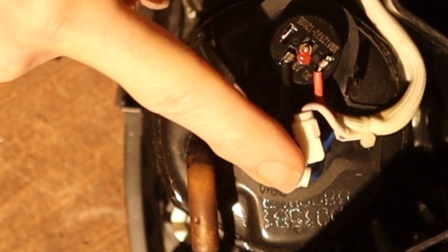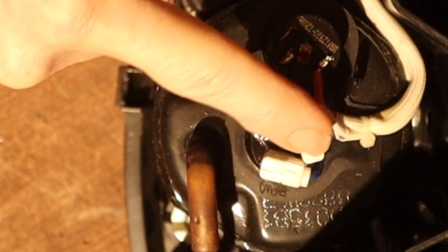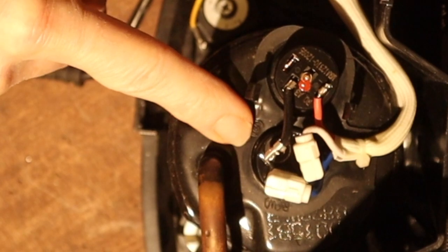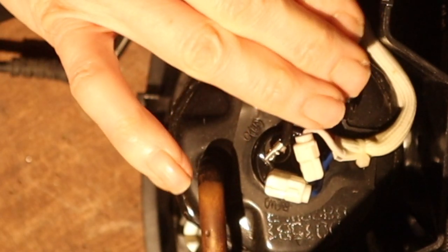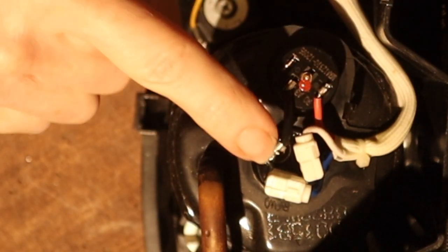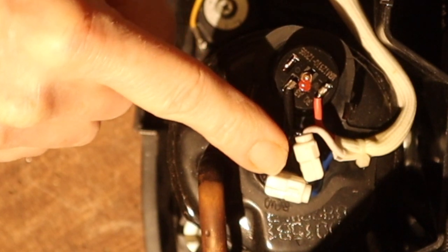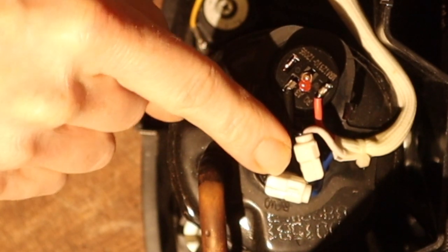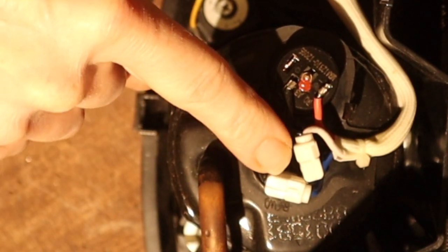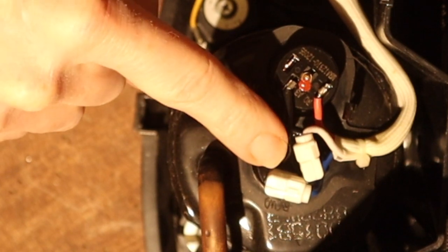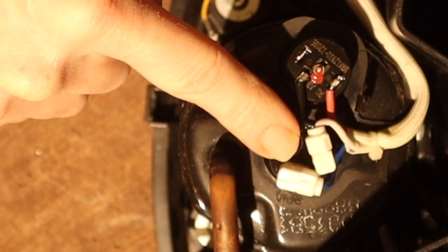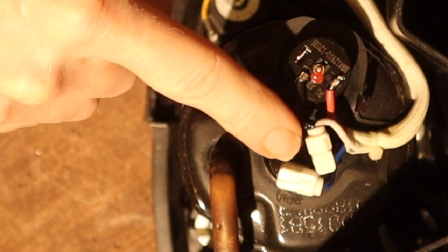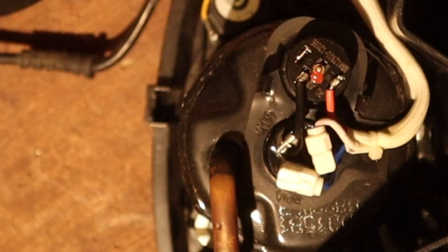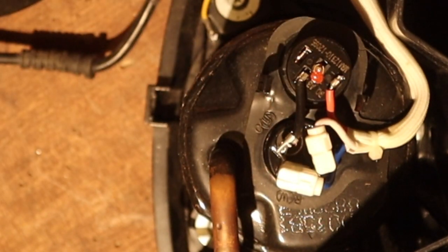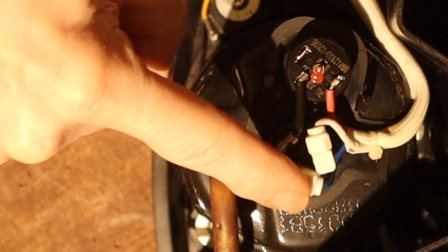So this is the phase shifted contact. The compressor itself, without this overload protection, has only 3 contacts, and that is because it has 2 windings, and one contact is shared between the 2 windings. So this is the shared contact, because this blue cable of the capacitor goes to here.